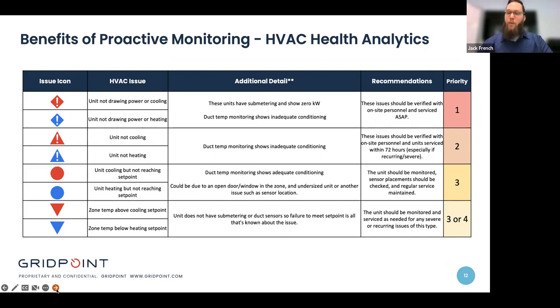And if that air is making its way to the space and the actual zone temperature is 75 degrees, they're 5 degrees above the cooling set point, which we're using 70 in this example. This could mean that the unit is undersized, so it can't provide a high enough volume of air to fully satisfy that set point in that zone. It could mean that there is an ambient heat source located too close to the thermostat or the zone sensor. And that could be in the form of an oven.